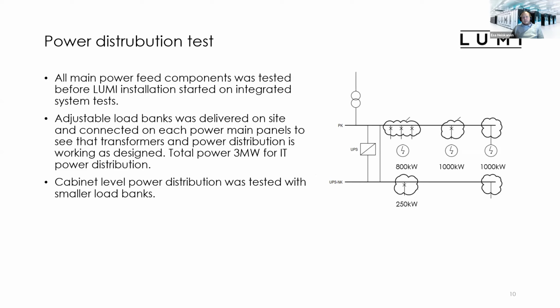We had a total of 3 MW of load banks installed in the power distribution, and here you can see how it was divided. We have 2 1 MW load banks directly connected to the main panel and 1 800 kilowatt on the main panel, and on the UPS side we have this 1 250 kilowatt heat load to see that our transformer can utilize its power and doesn't get overheated at full capacity, and that the UPSs are also working as designed with the full load. On the cabinet level, we also did this power distribution test with smaller load banks installed in the data center itself. So it was tested at all levels of power distribution before the Lumi installations.